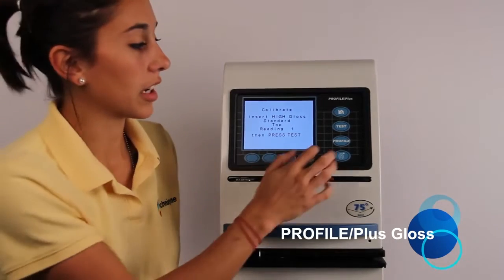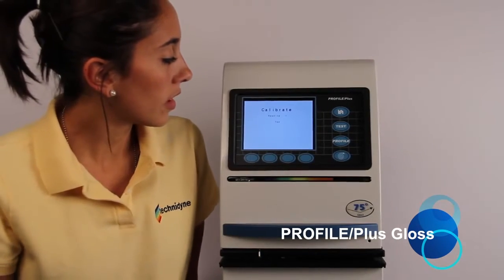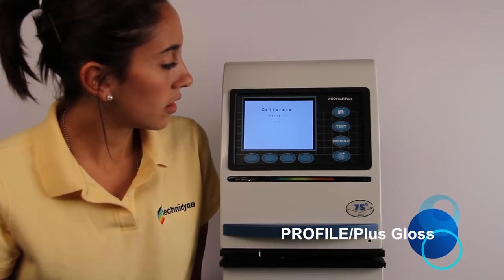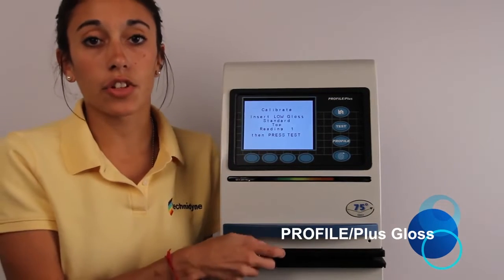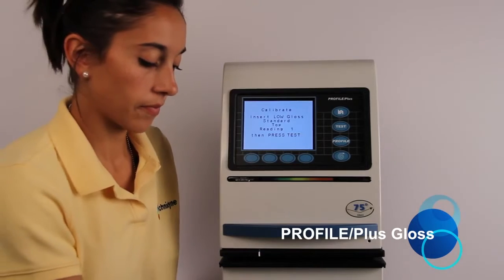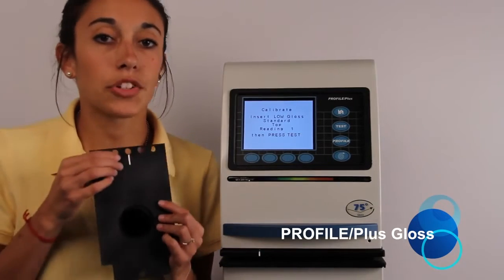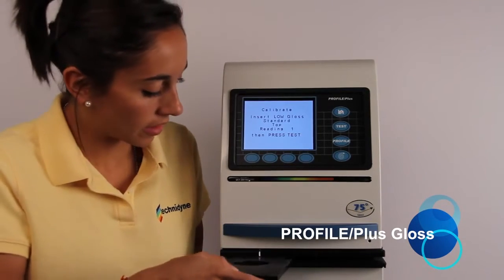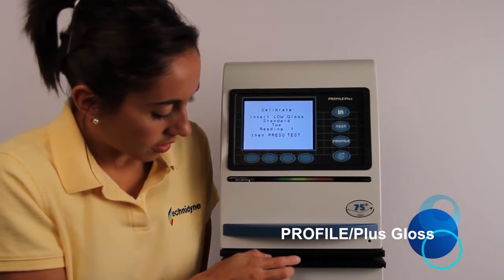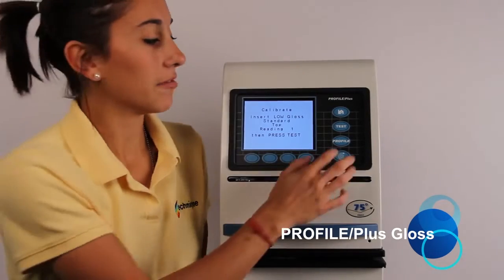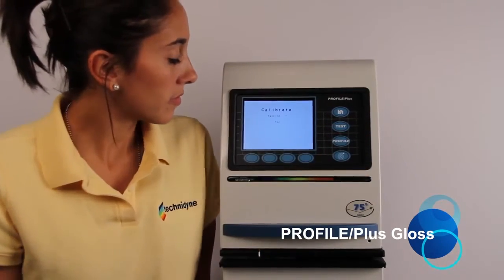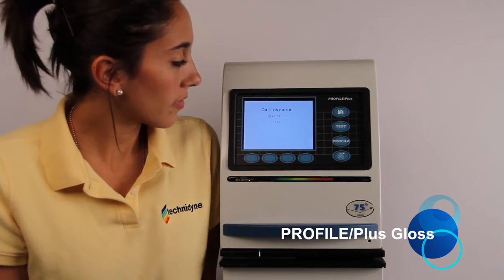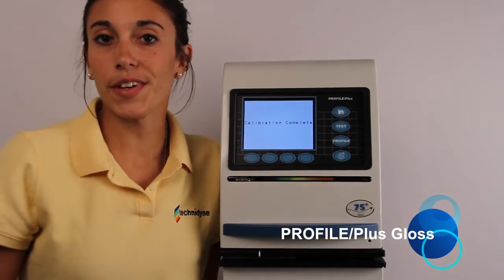And we'll press our test hard key. Next, it'll ask us to load our low gloss standard. Once again, you just want to make sure that the white lines match up. And we'll press the test key. Once it's finished reading, your calibration is complete.